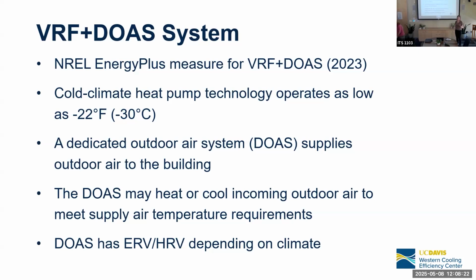Some of the past DOAS models for EnergyPlus only did cooling. This does both. The heating is supplied with electric resistance elements, and there is mention in the report of potentially switching that out for heat pumps later on, which would make the system more efficient. It also has an energy recovery ventilator or heat recovery ventilator, depending on the climate. If it's humid, it will be energy recovery. If it's dry, heat recovery.